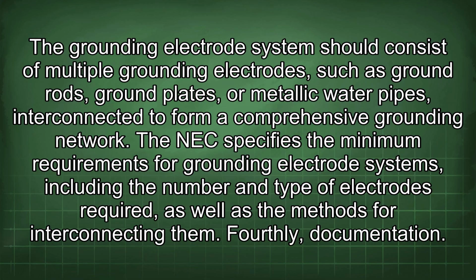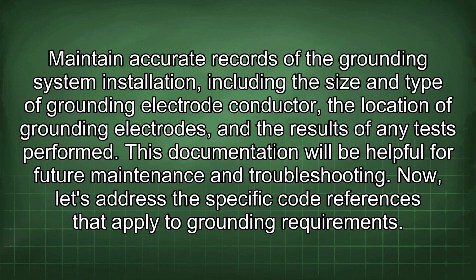Fourthly, documentation. Maintain accurate records of the grounding system installation, including the size and type of grounding electrode conductor, the location of grounding electrodes, and the results of any tests performed. This documentation will be helpful for future maintenance and troubleshooting. Now, let's address the specific code references that apply to grounding requirements.